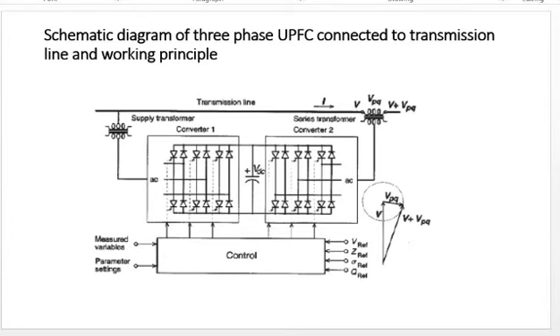We can analyze that voltage source converter one can also generate and absorb controllable reactive power if required, and hence it provides independent shunt compensation for the line. Thus, voltage source converter one can be operated at unity power factor or be controlled to have reactive power exchange with the line, independent of the reactive power exchanged by converter two.